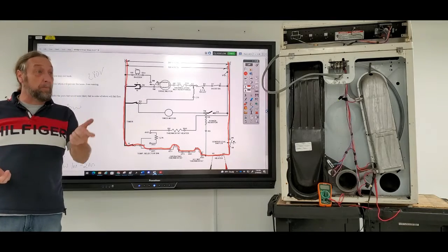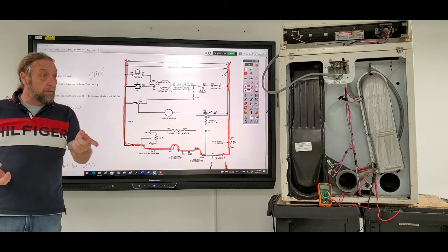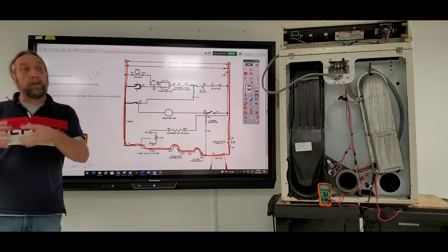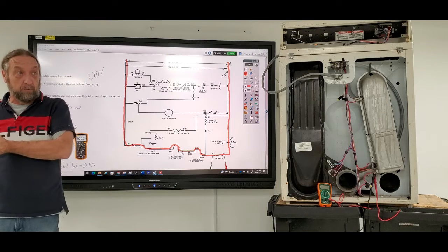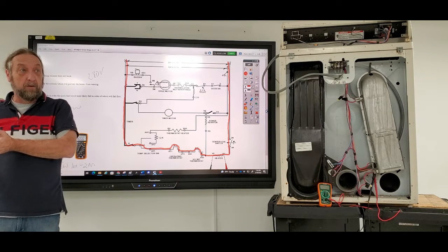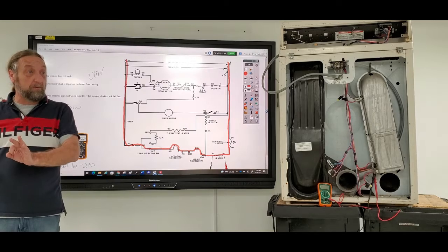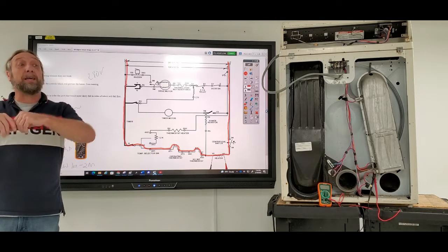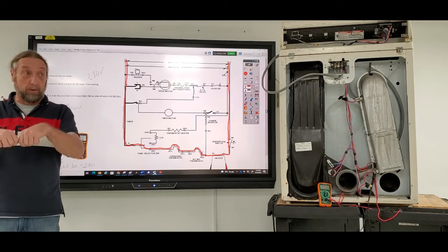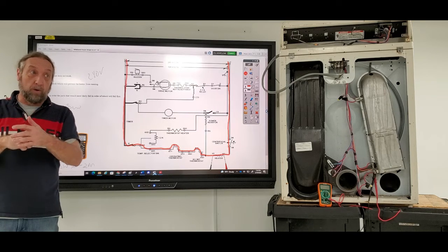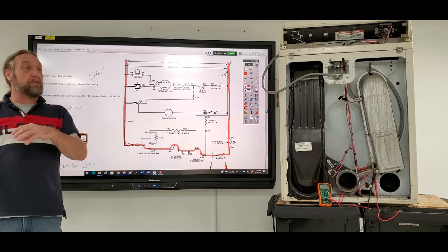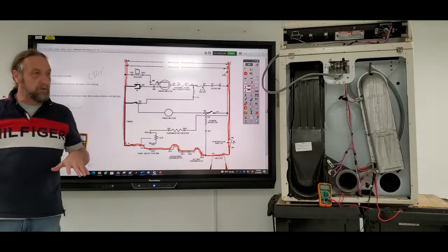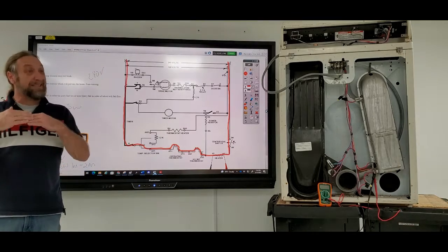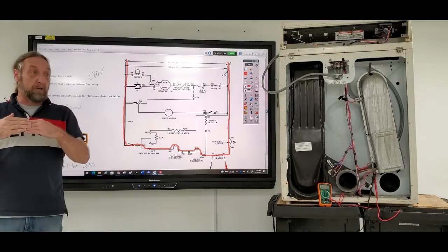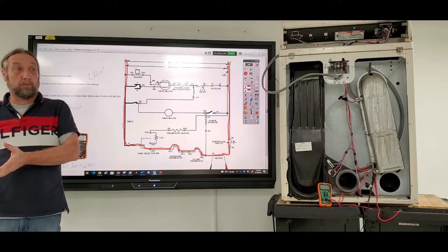No, it would be open. Short would be like a short circuit, and it would blow a fuse. You said H1 to H2, I have 240 volts. So that means my heater is broken. It's open, not shorted. So when you use the term short, I see what you mean. That means it had a resistance value, and now it has no resistance. It's 0 ohms, like a door switch, for example, and that would be a short or a shunt.